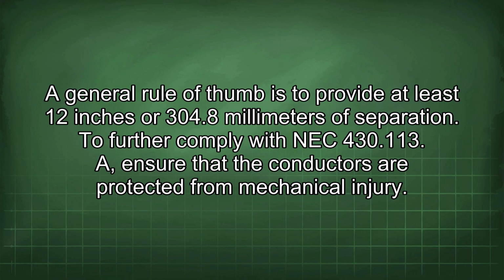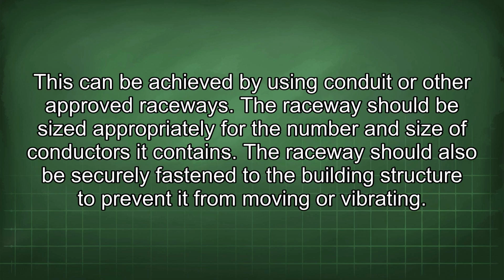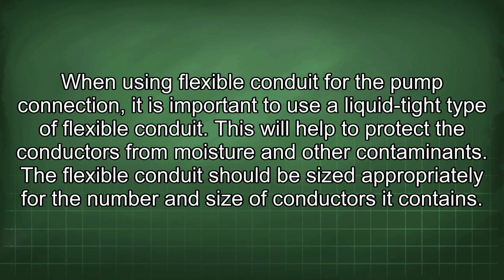To further comply with NEC 430.113(A), ensure that the conductors are protected from mechanical injury. This can be achieved by using conduit or other approved raceways. A raceway should be sized appropriately for the number and size of conductors it contains. The raceway should also be securely fastened to the building structure to prevent it from moving or vibrating. When using flexible conduit for the pump connection, it is important to use a liquid-tight type of flexible conduit.